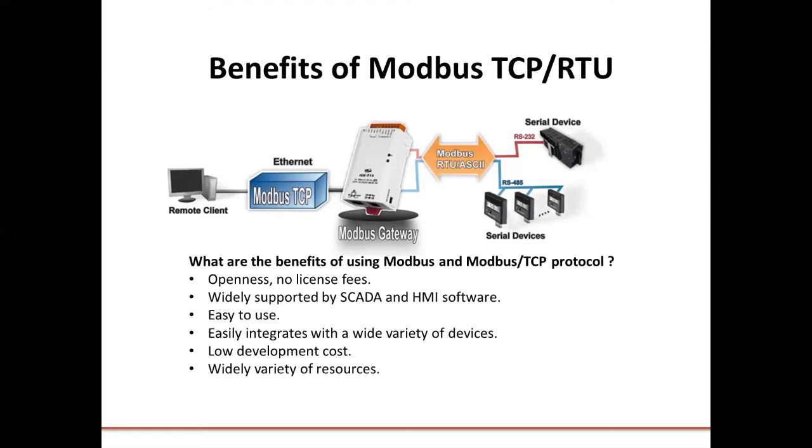Say, for instance, you had different pieces of machinery, all identical. They would connect to a similar array of sensors and data acquisition modules on the machine, which can be connected serially. And then you can use a TGW module to convert the communication to Modbus TCP to add to your network to make it simpler to connect all these machines to the central computer for data logging and data acquisition.